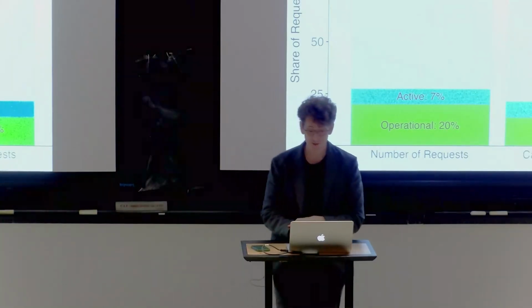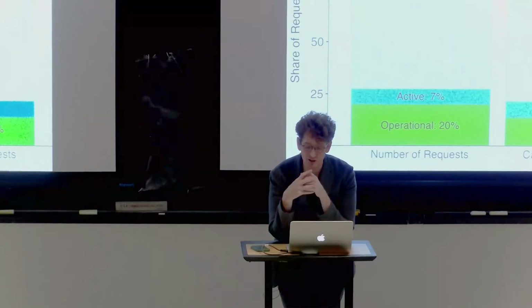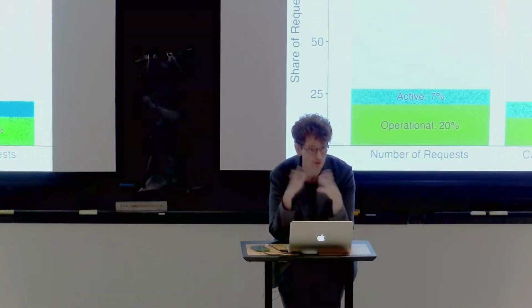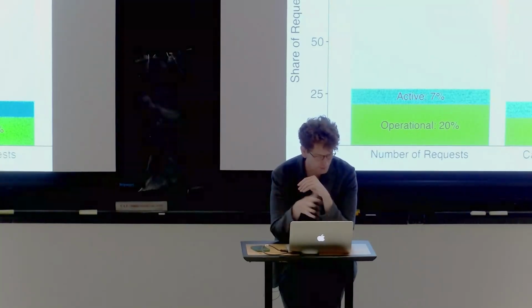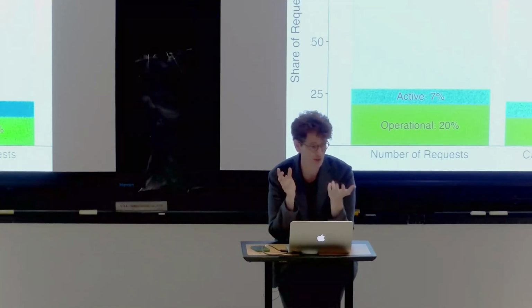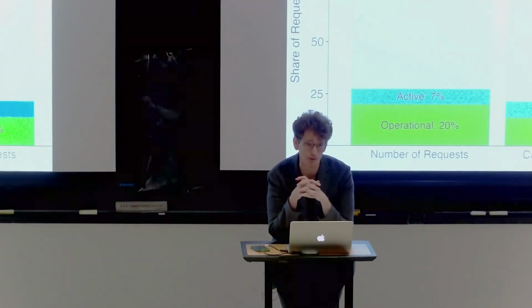In case you're wondering how expensive this is, typically the point of interconnection charge is something less than $50 per kilowatt in terms of capital expenditure. I'll have a plot at the end, so just remember that. Whereas a network upgrade would be something like $200 or $300 per kilowatt of capacity. So it depends on the project, but it's a considerable addition to the cost of these things.